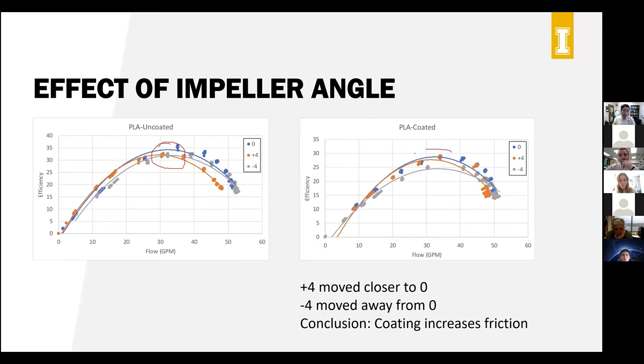But if you look at this coated impeller, the opposite happened. The orange one moved closer to the blue one, that is +4 moved toward the blue one, and the -4 moved away from it. So that could happen only for one reason: coating the impeller did not reduce the friction, it actually increased the friction. So that was our conclusion from this test.